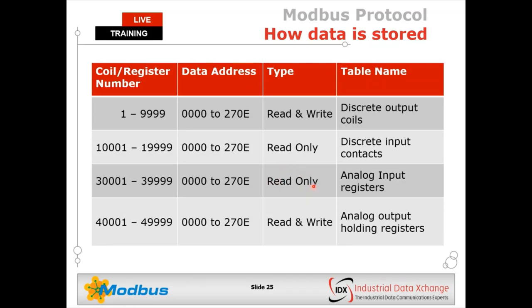Analog input registers are read-only — the controller can only read information stored in the IO device from the 30,000 table. Analog output holding registers allow the controller to both read and write information to devices. If you want to write a setpoint to a thermostat in the field, use an analog output holding register. To read temperature, use an analog input register. The information available within specific devices is specified in the Modbus user manual, which tells you which table stores which pieces of information.